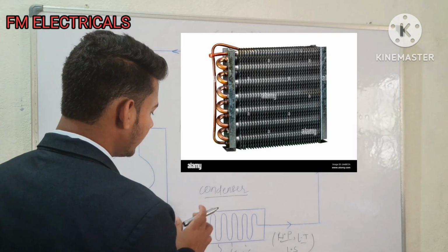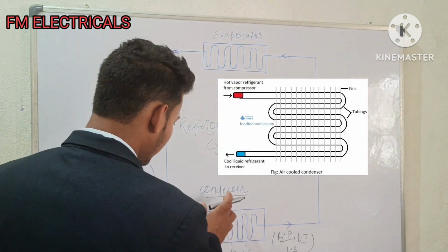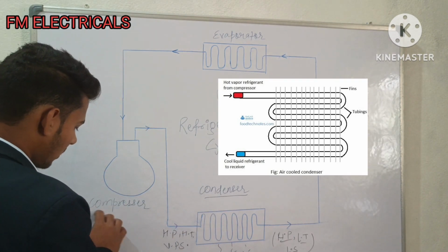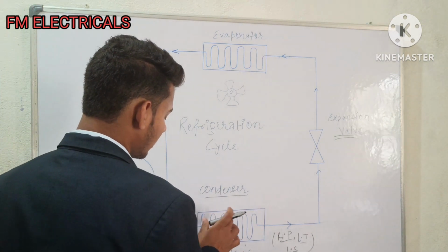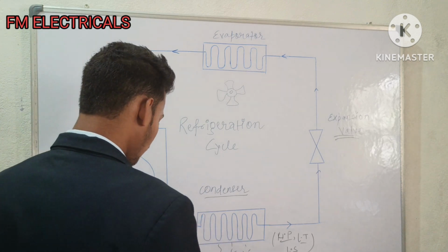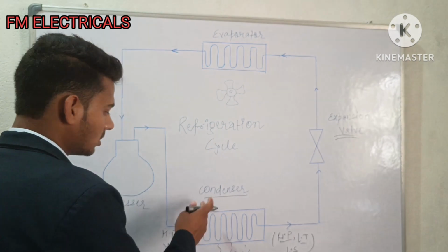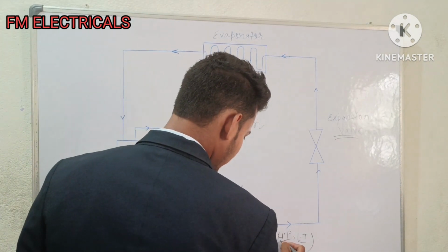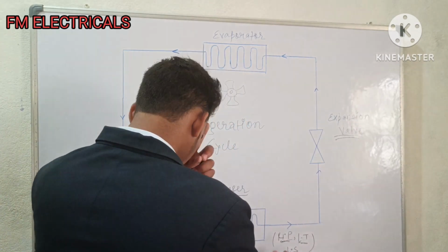The condenser coil is a heat exchanger in the refrigeration cycle. The condenser coil cools the refrigerant coming from the compressor at high temperature. As the heat in the refrigerant is released, the refrigerant changes from vapor state to liquid state. When it comes out of the condenser, the refrigerant is at high pressure, low temperature and in liquid state.